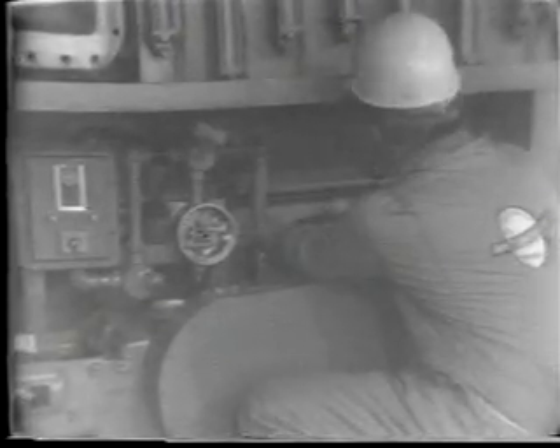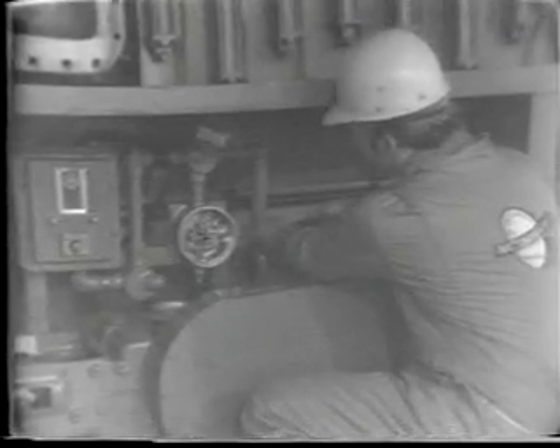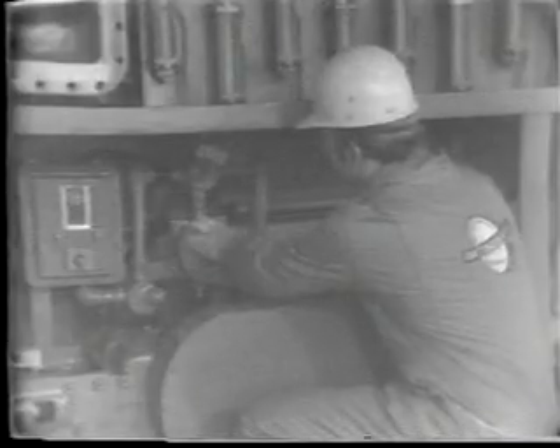The only pressure switch not located in the left-hand explosion-proof box is the one for the electrical operated pump. This pressure switch is adjusted exactly the same way as the accumulator alarm switch. It is located on the front of the pump unit close to the electric pump. Its purpose is to automatically start and stop the electric pump at the system's operating pressure.